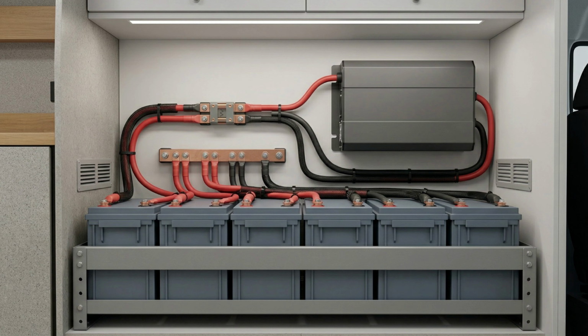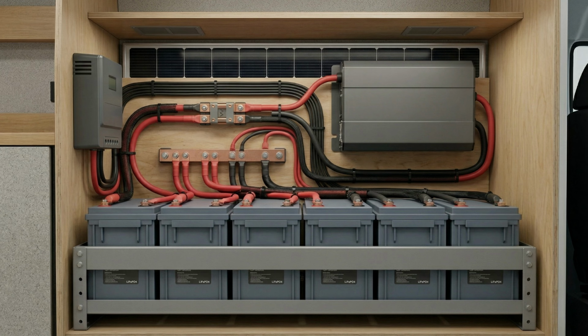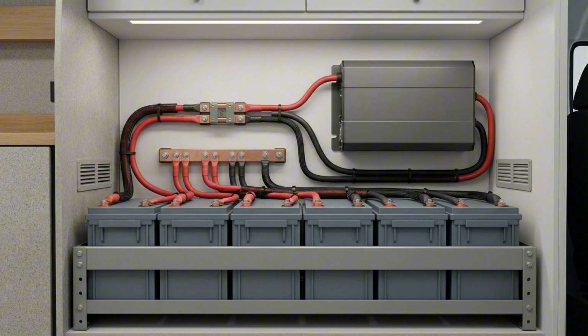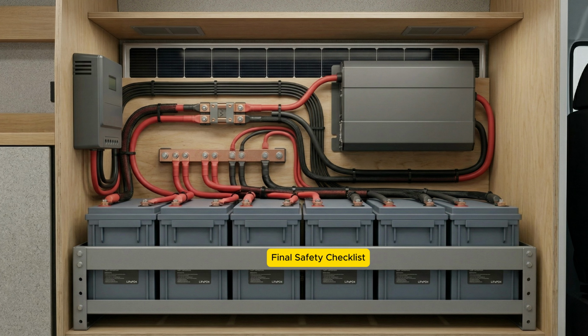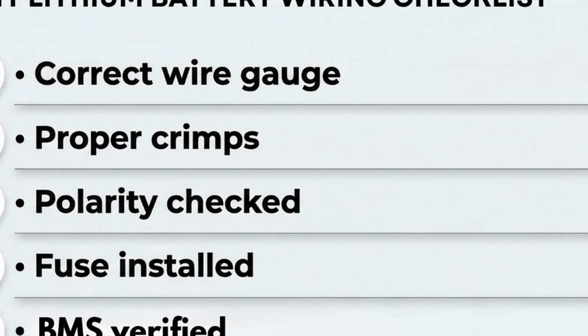Every positive cable leaving the battery should have a properly sized fuse or breaker installed as close to the battery as possible. That placement matters. The point is to protect the wire from the very beginning of the run. Skipping this step puts the entire system at risk. And it is one of those mistakes people often regret only after something goes badly wrong.